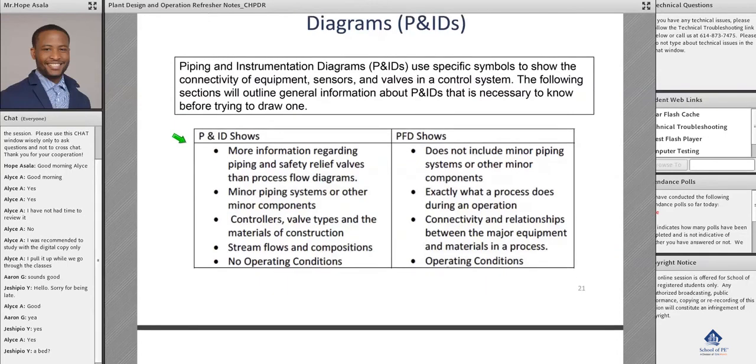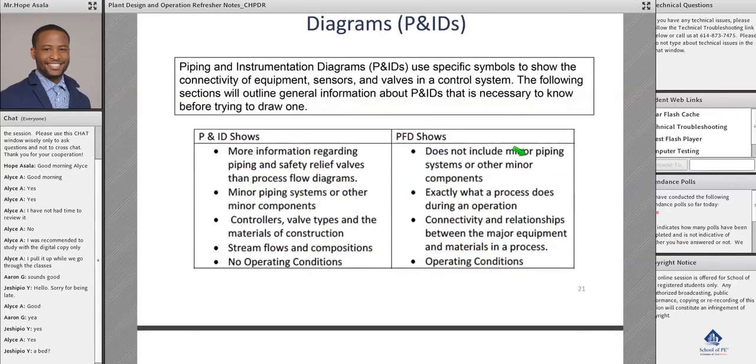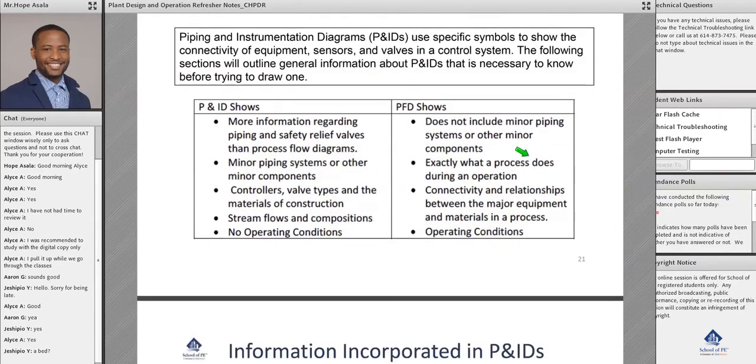The P&ID has more information regarding, in my opinion, the peripheral systems. It's going to tell you more about the piping and safety valves, and if there's controllers somewhere in the system. It's going to tell you more about the minor peripheral things in the system that we need to know and are important for safety, but would clutter the whole PFD diagram. So the PFD excludes minor piping components that are not really crucial.